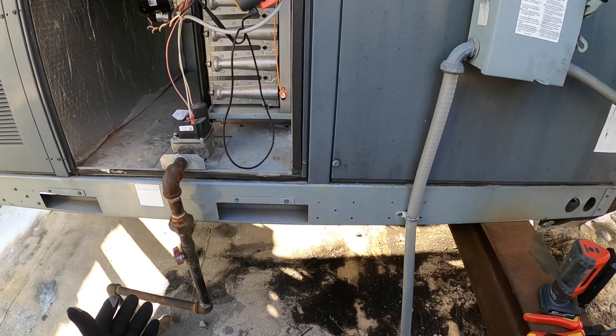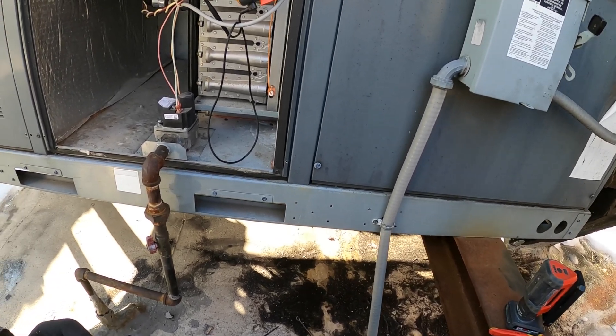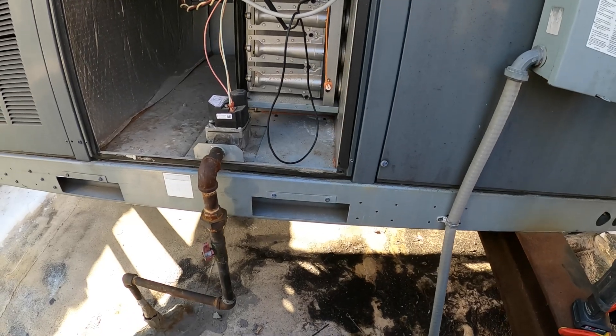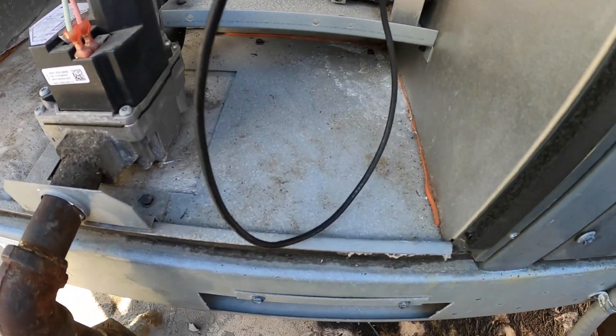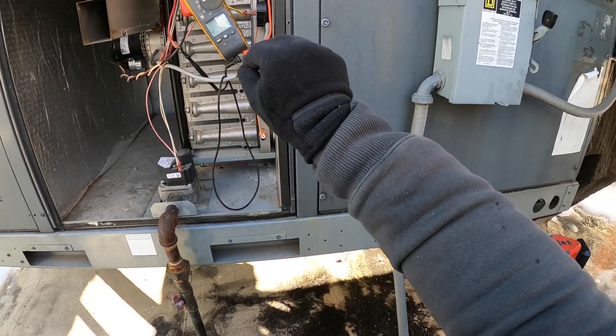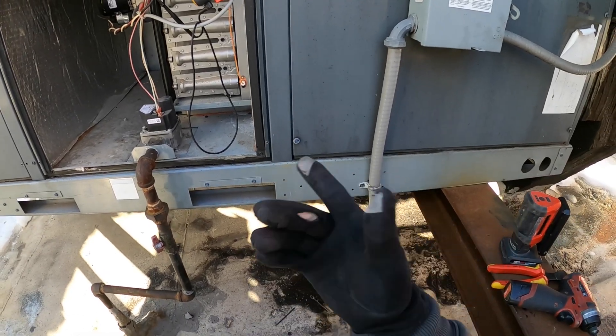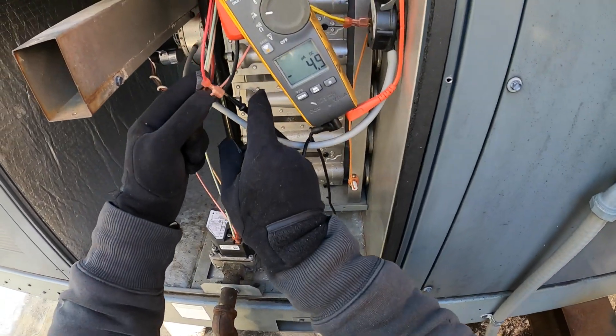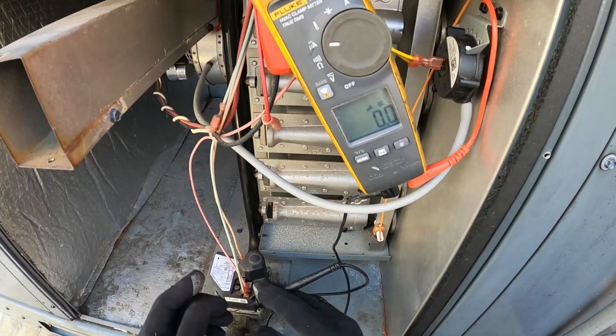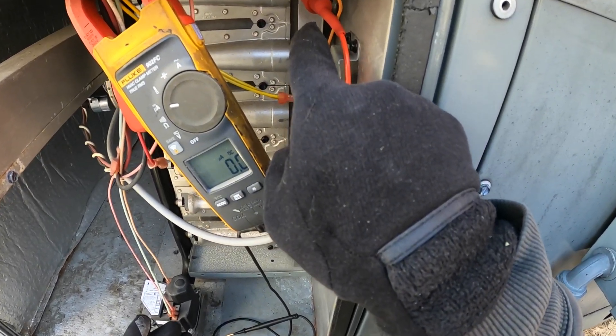Take a look at the physical condition of it. A lot of the time these things just need to be cleaned, but after some time it's better to just get it replaced — you're not going to get away with cleaning it up with a little scotch pad forever. Another thing you want to do is: when you remove the wire, you want that flame to stop. Right there I pulled out the wire, which was basically like pulling out the wire from the control.